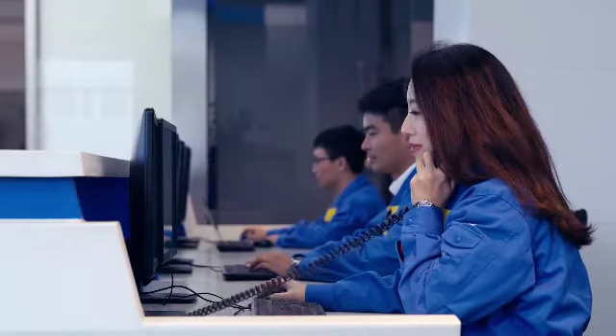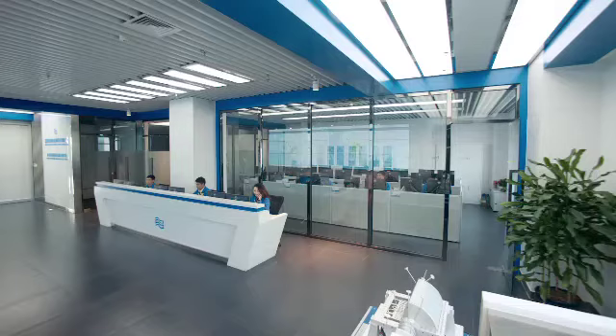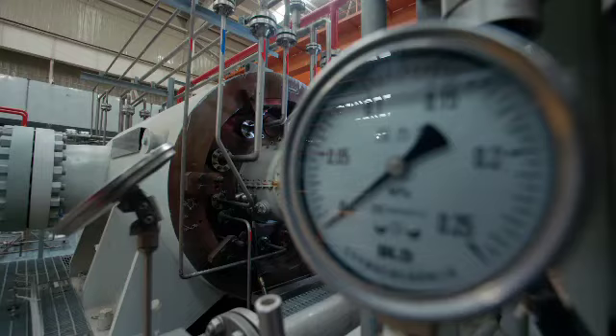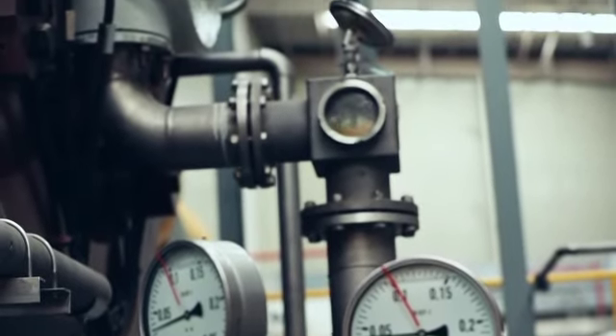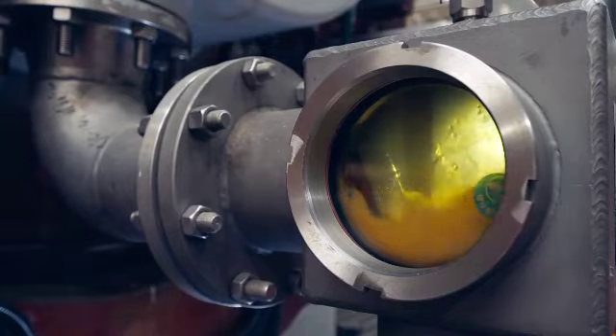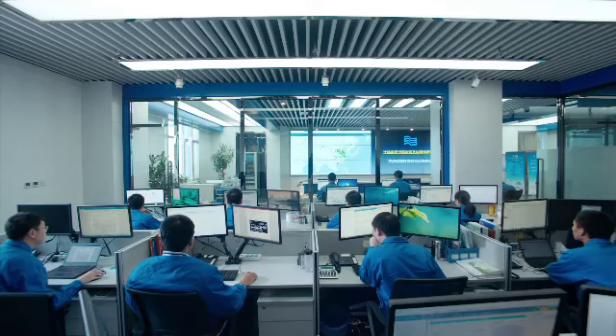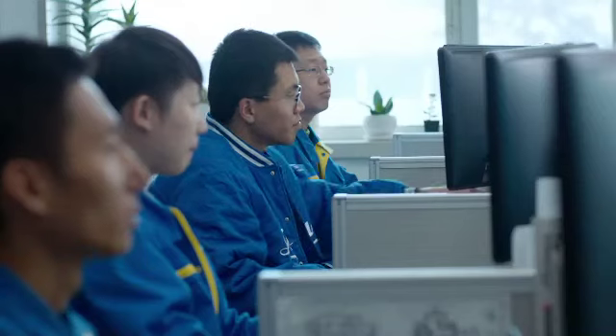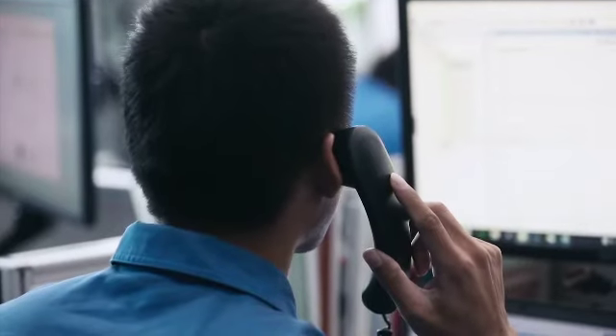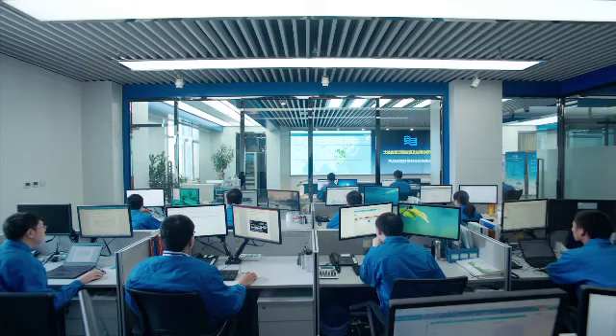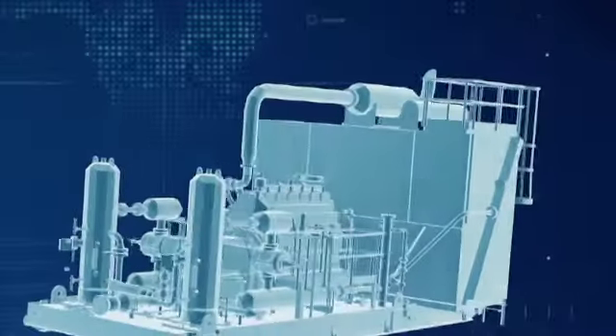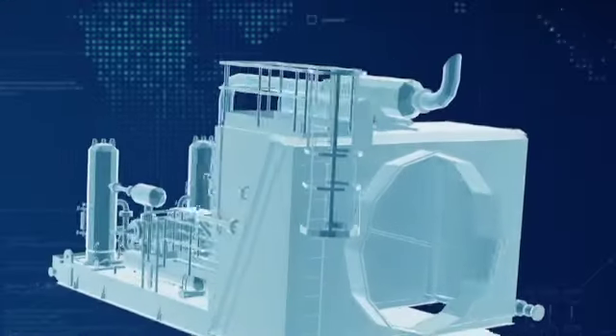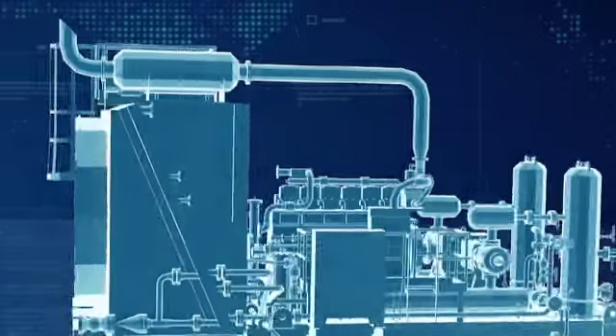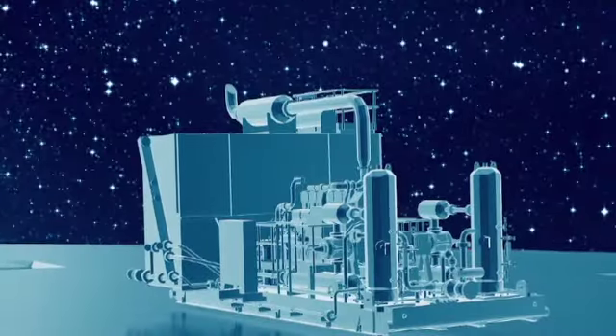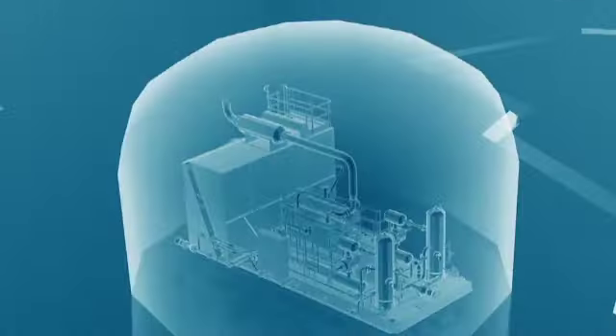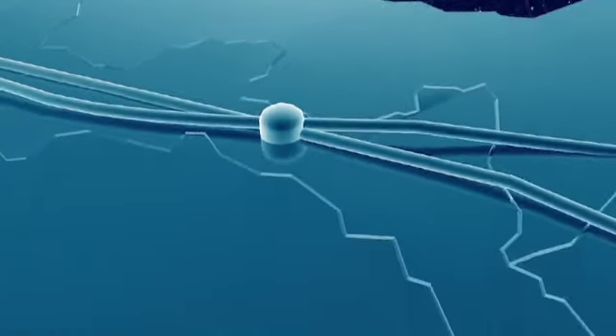Their monitoring can be achieved thanks to a remote system called Shanggu Cloud. Sensors installed in key parts of the compressor transmit its operating data in real time to the remote monitoring system. Through it, engineers and technicians can see clearly how the equipment they've made is running throughout the country and take immediate action if there's an alert. In China, more than 2,000 such compressors have already been made. They are now delivering 16.5 billion cubic meters of natural gas yearly to cities and remote areas.